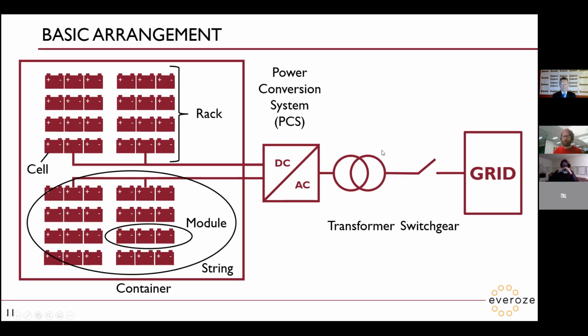Then we have a transformer. This is the electrical symbol for a transformer, and that's just to step up the voltage to things the grid likes. Usually on the output from the PCS, you'll be at about 600 volts, maybe 400. Here you'll often be at 33,000 volts. Your house is about 230 volts. So even here we're usually at a higher voltage than an average domestic supply, but here we're substantially higher, about 33 kV, sometimes 11 kV.